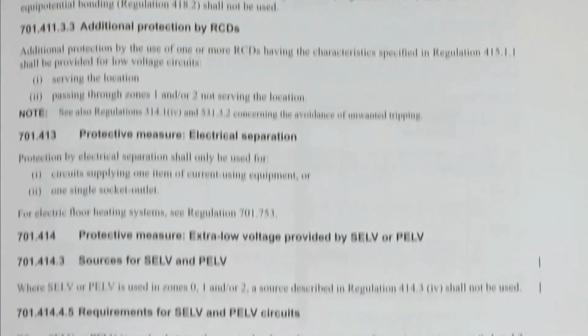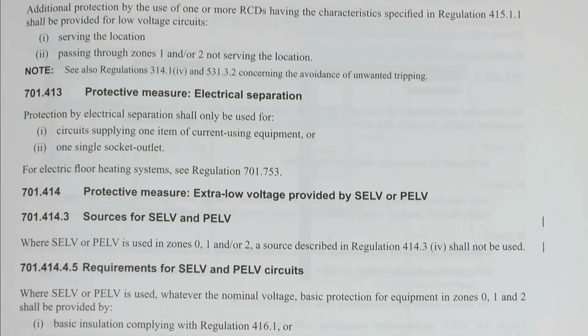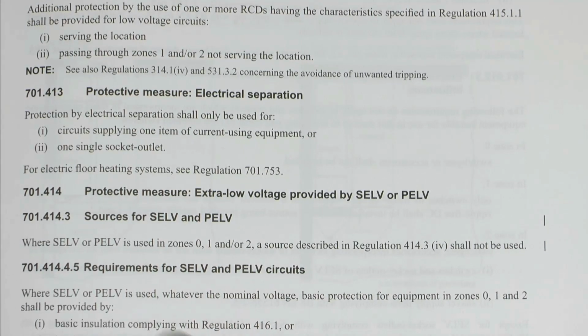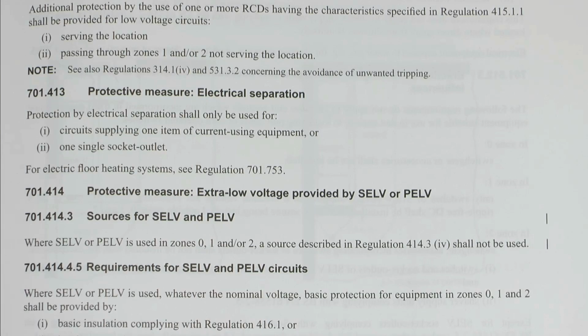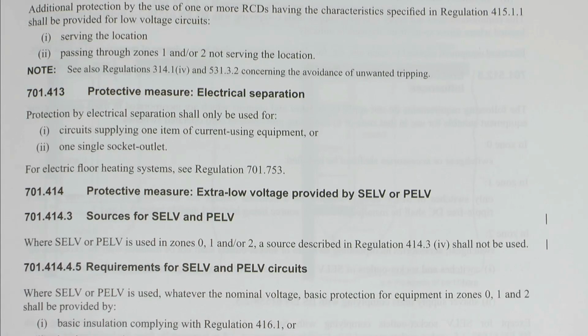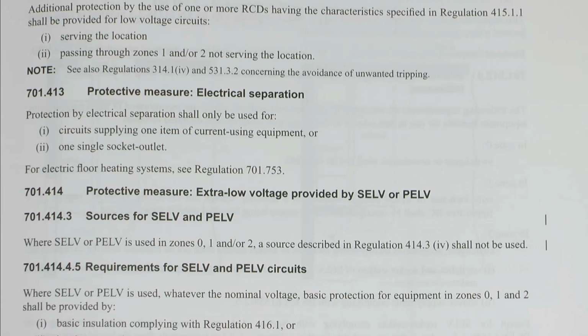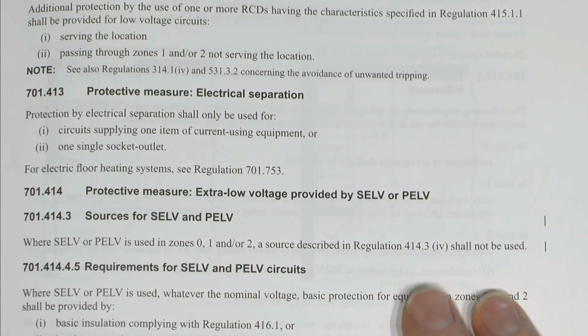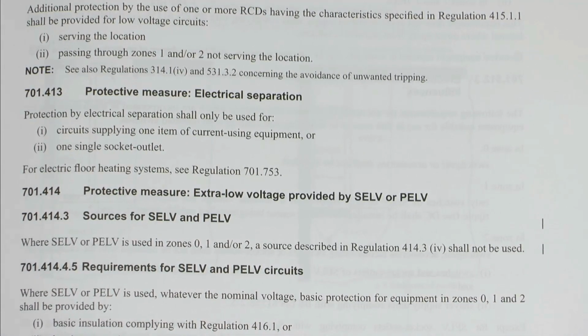And first thing on the list here is 701.414.3. This is new, been added in, and where SELV or PELV is used in zone 0, 1 or 2, a source described in regulation 414.3 indent 4 shall not be used. Now this particular sentence actually appears in a variety of other chapters in Part 7, and it basically is all the same thing, and basically you can't use what's described in 414.3. So let's have a look what that is.